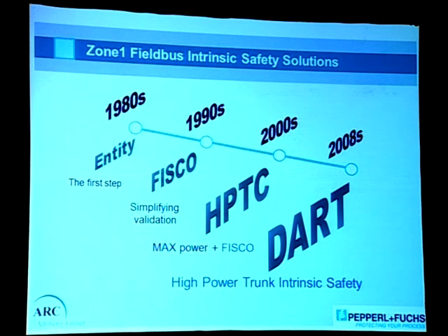So the PTB authority, together with a few other companies, P+F is one of them, came out with a new concept that is going to be applied only in Fieldbus applications. It still follows intrinsic safety, but only in Fieldbus applications. So we made some improvements and came out with the Fieldbus intrinsic safe concept. That was introduced in the early 1990s, and it still has some limitations. It's better than the conventional type of intrinsic safety, but of course it still has some limitations. We still need to limit the energy, the voltage and the current, and it is not sufficient to meet all the criteria we just saw.